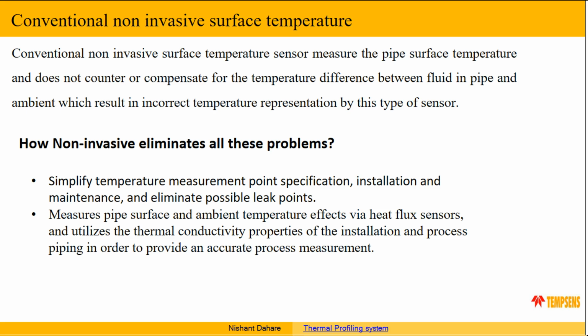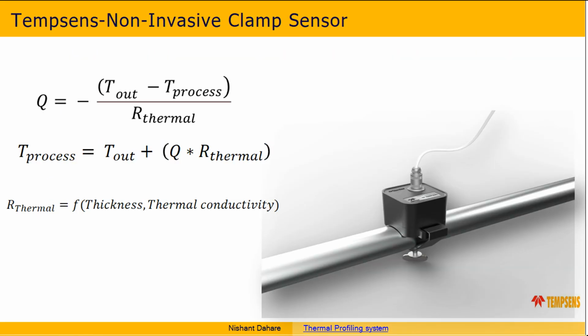This is the basic analogy behind the working of this clamp sensor. This is an inverted image of the sensor - generally it will be below the pipe, because due to gravity, fluid is always in the lower part of the pipe, so you need full contact with the pipe where the fluid is traveling.